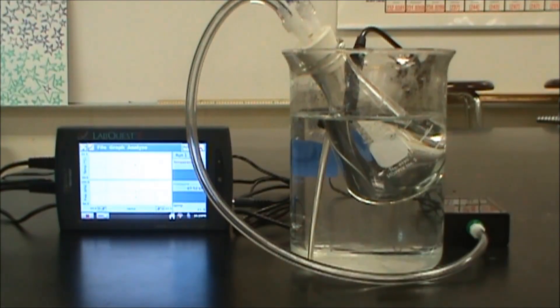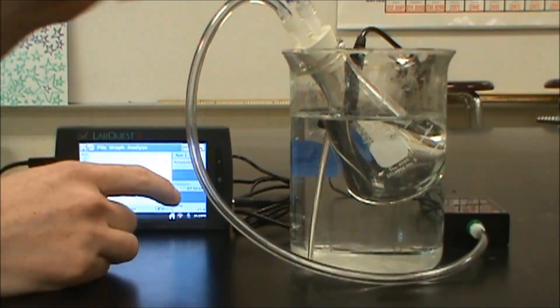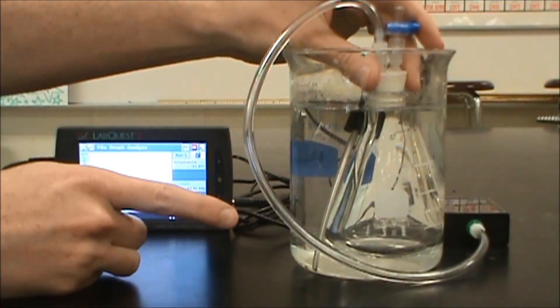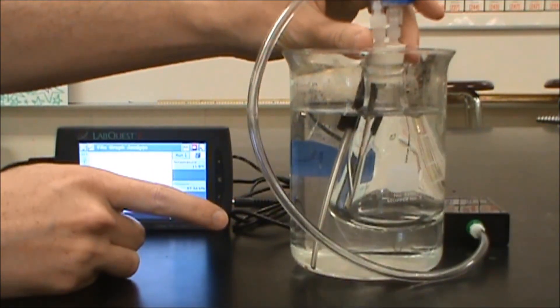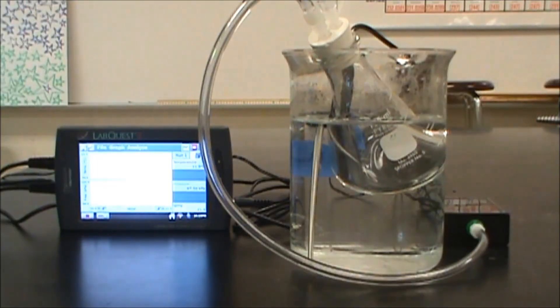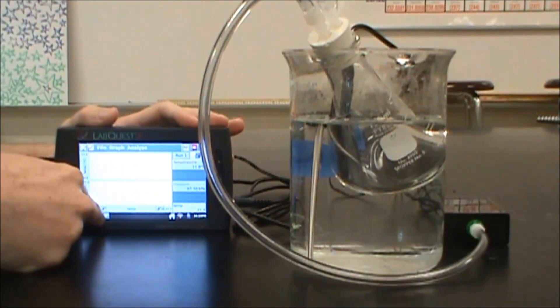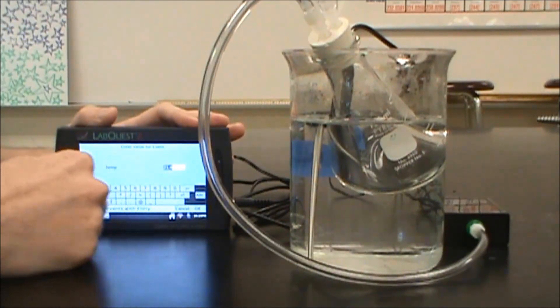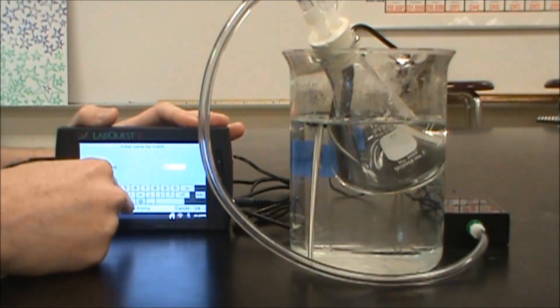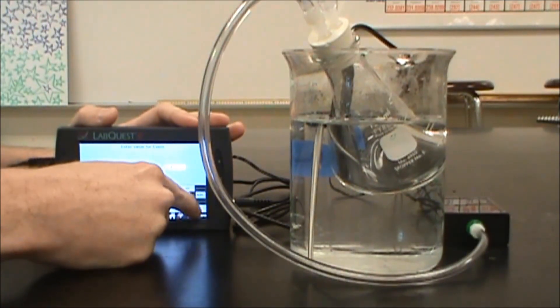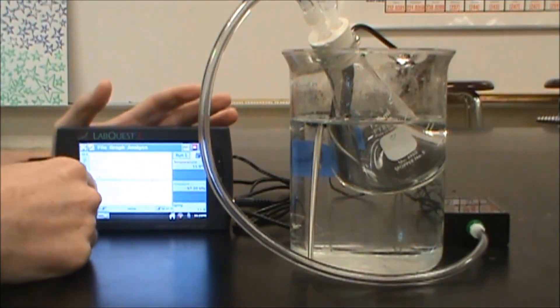When you've done this for long enough and you're satisfied that both the temperature and the temperature of the gas inside and the temperature of the water are the same, then you're going to go ahead and hit keep again. Currently my temperature reading is 11.8. So I'm going to hit keep, type in 11.8, hit OK. Now I have my two data points.